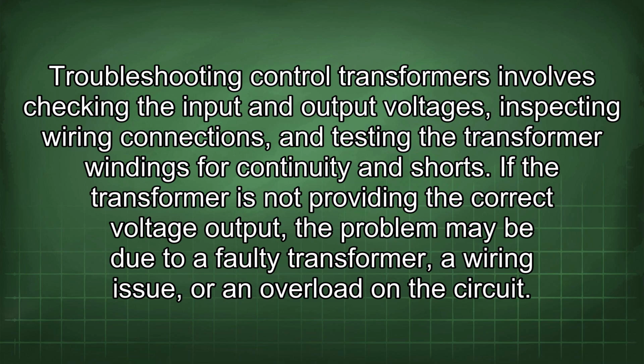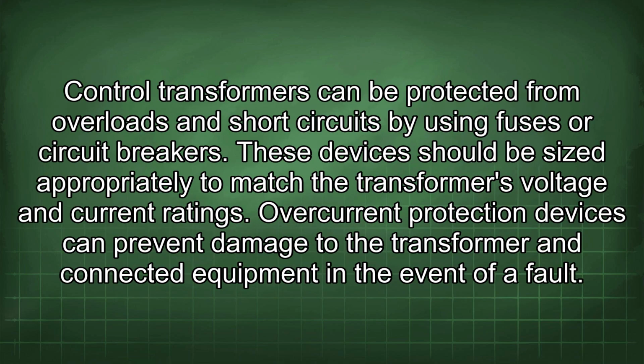continuity and shorts. If the transformer is not providing the correct voltage output, the problem may be due to a faulty transformer, a wiring issue, or an overload in the circuit. Control transformers can be protected from overloads and short circuits by using fuses or circuit breakers. These devices should be sized appropriately to match the transformer's voltage and current ratings. Overcurrent protection devices can prevent damage to the transformer and connected equipment in the event of a fault.